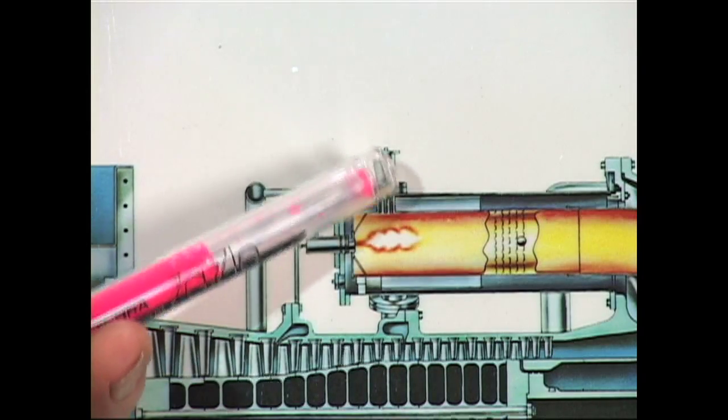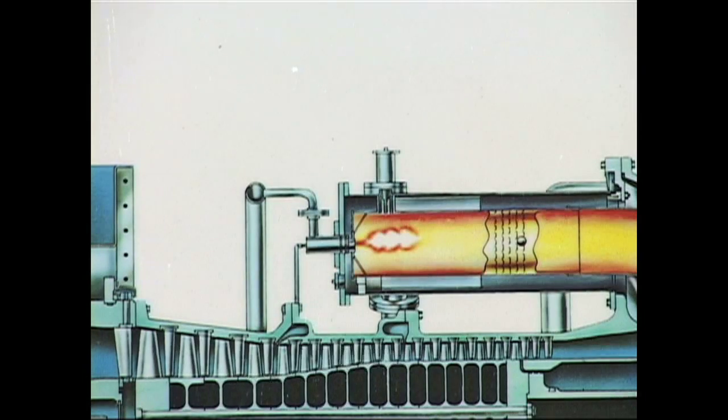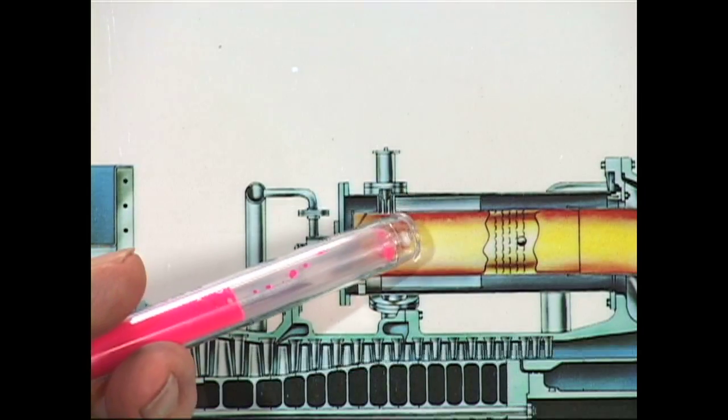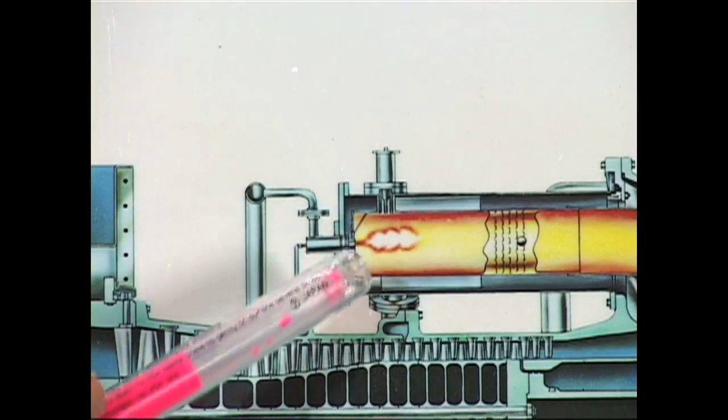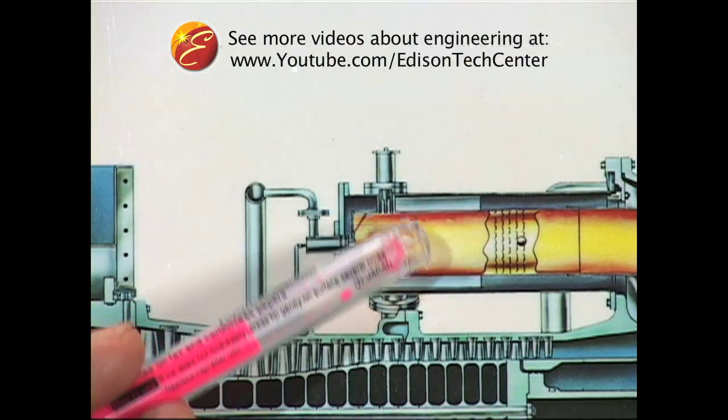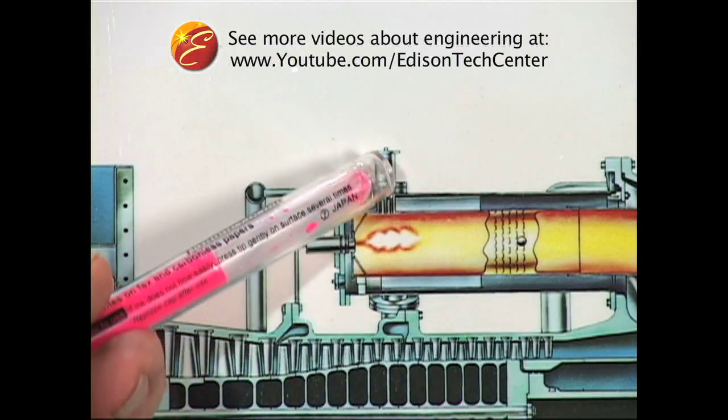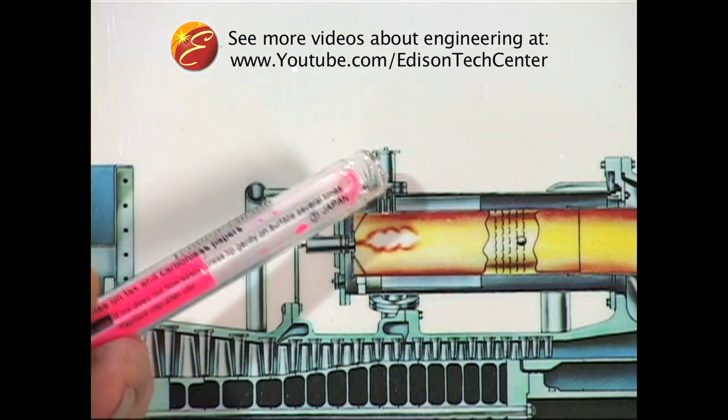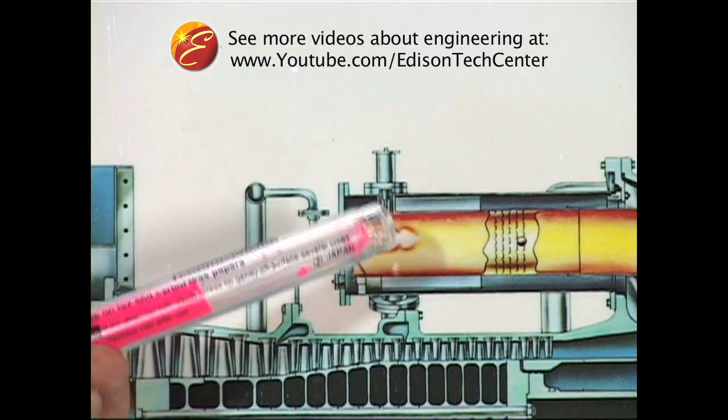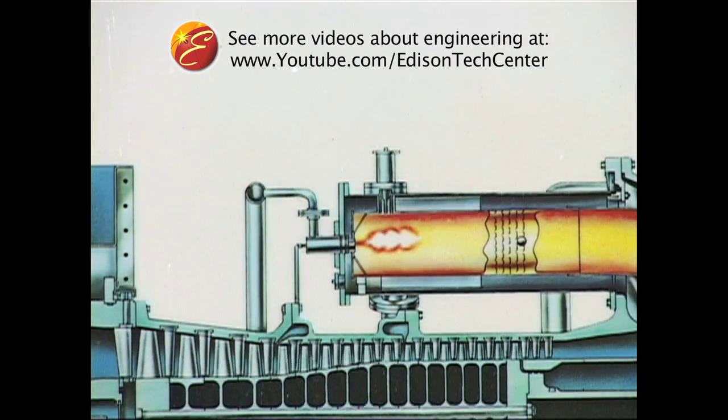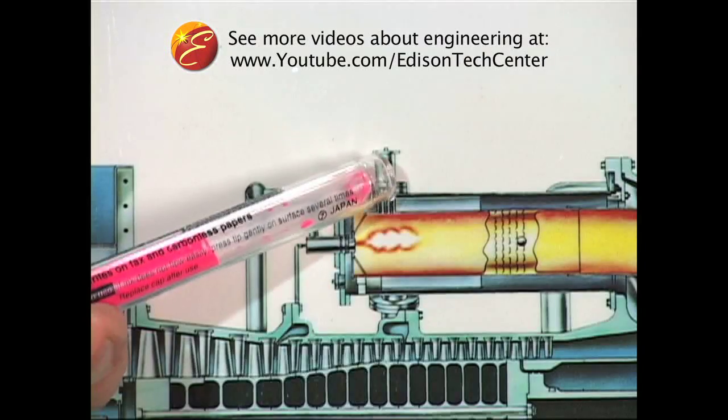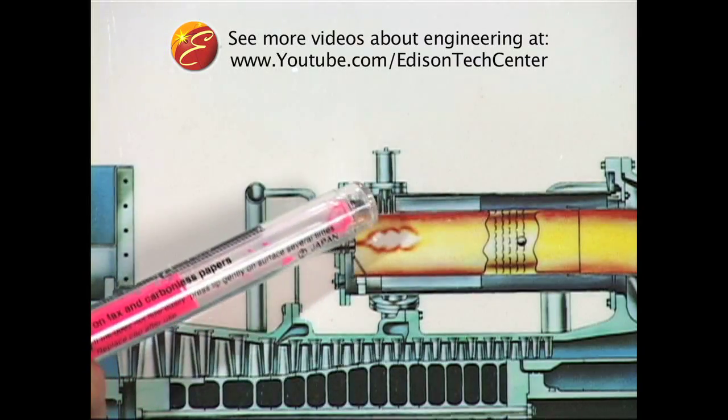The spark plugs are out of the picture because they are pressure ejected out of the way. But the flame detector keeps on sensing what's going on. And it's always tricky to make sure that we don't cut the fuel back too far. If we cut back too far, the flame will go out and the flame detector is in the protection that says, hey, shut down again. So normally that does not happen. But if it does, we must shut down. Otherwise we put fuel in and no fire and pretty soon you have an explosion. So these flame detectors are a very important part of the starting cycle.